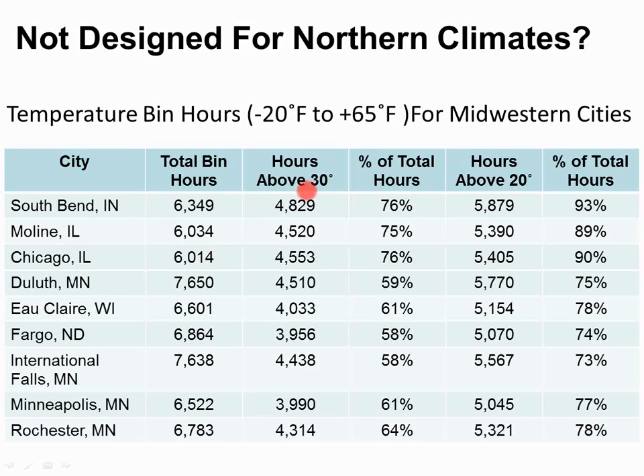What I want you to focus on here is look at the hours above 30, the heating hours above 30. So when is it between 30 and 65 outside? In South Bend, 4,800 hours, which is 76% of the heating hours, it is above 30 degrees outside. But look at above 20, so between 20 and 65, it's 5,900 hours, which is 93% of the hours. 93% of my heating hours, it is above 20 degrees outside.